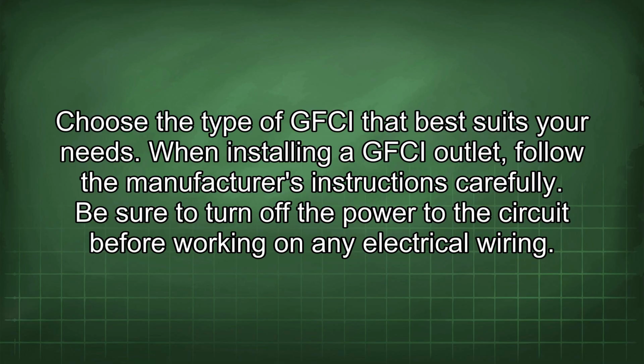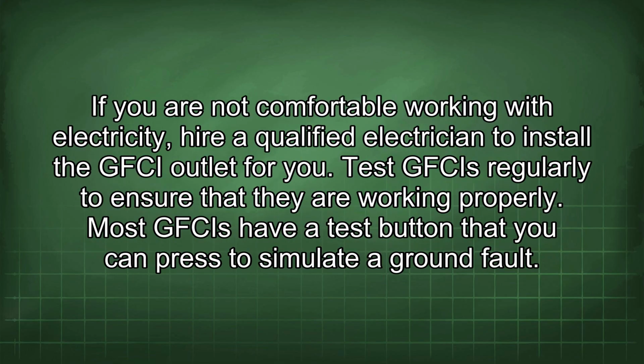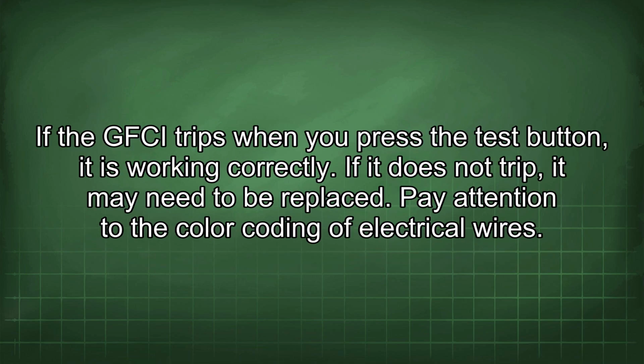When installing a GFCI outlet, follow the manufacturer's instructions carefully. Be sure to turn off the power to the circuit before working on any electrical wiring. If you are not comfortable working with electricity, hire a qualified electrician to install the GFCI outlet for you. Test GFCIs regularly to ensure that they are working properly. Most GFCIs have a test button that you can press to simulate a ground fault. If the GFCI trips when you press the test button, it is working correctly. If it does not trip, it may need to be replaced.